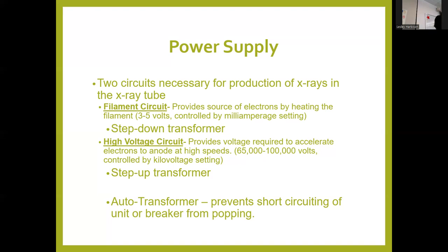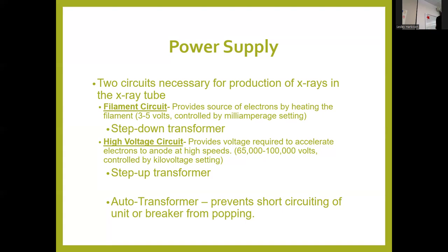When you push the button you need high voltage to accelerate the electrons across to the anode. A high voltage circuit provides the voltage required to accelerate electrons to the anode at high speed — you need 65 to 100,000 volts, way more than 110 coming out of the wall. So because you're going from 110 up to 65,000 or 100,000 volts, you need a step-up transformer. There's also an auto transformer that basically evens everything out, keeps things from short circuiting, and prevents extreme voltage variations from popping a breaker.